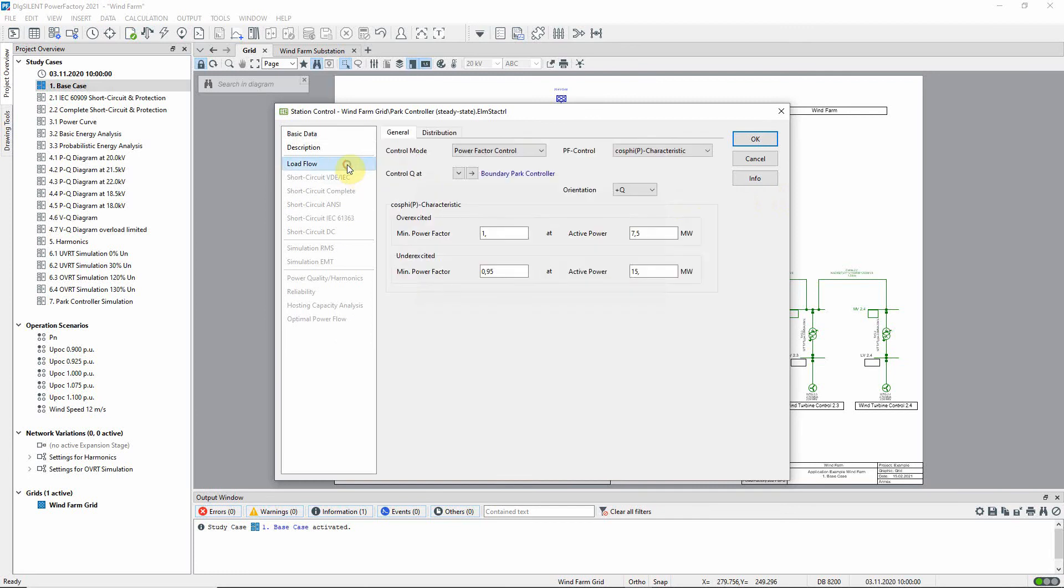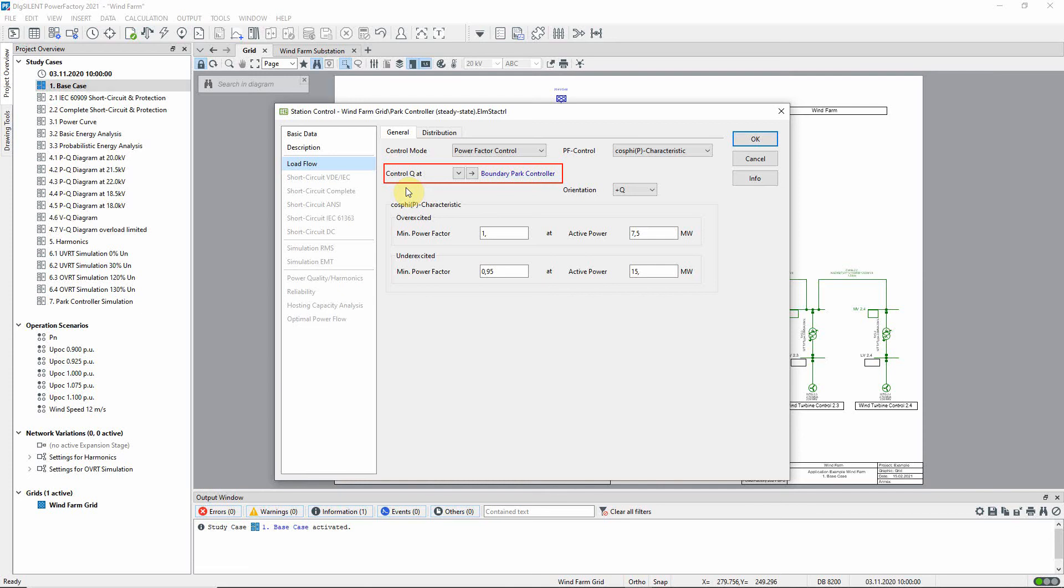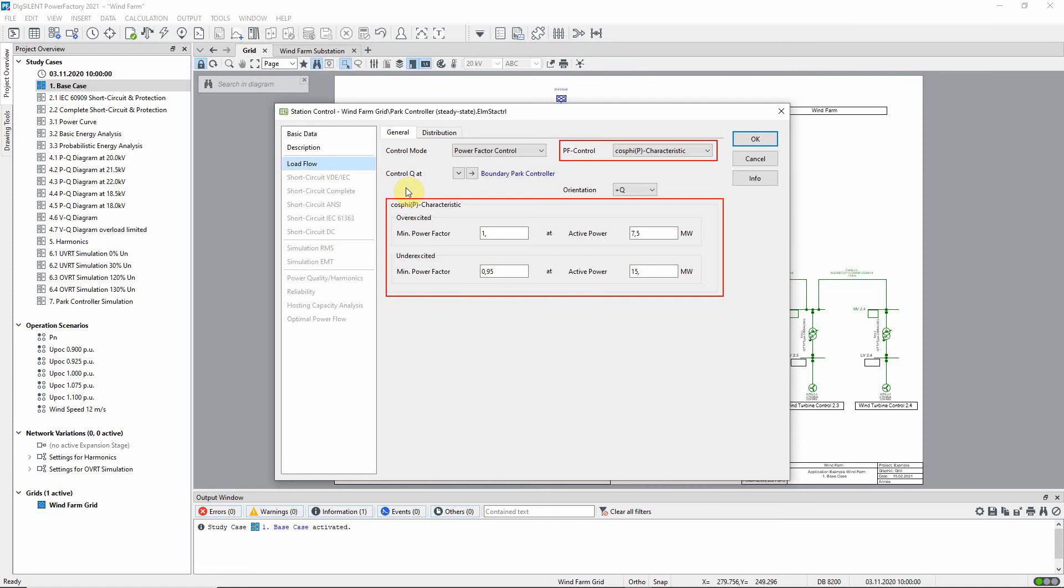On the load flow page we see that the control mode is set to power factor control, and the point in the network at which the power factor is controlled is shown here. The station controller applies a cos phi as a function of P characteristic. When the active power at the controlled node is 7.5 megawatts or less, the over-excited power factor is set to one. When the active power at the controlled node is 15 megawatts or more, the under-excited power factor is set to 0.95. Between these active power setpoints the power factor decreases linearly.